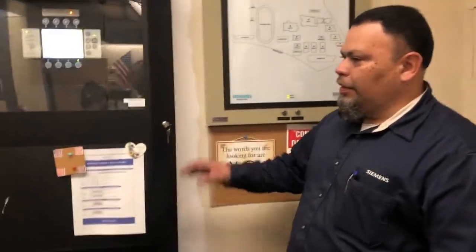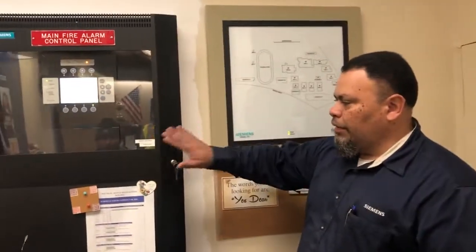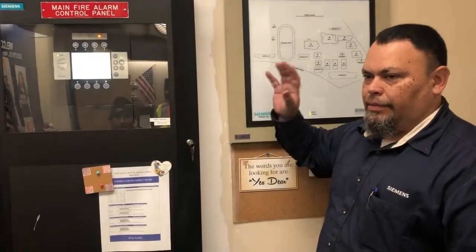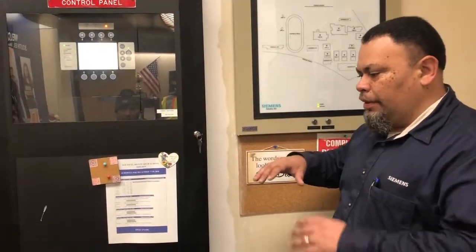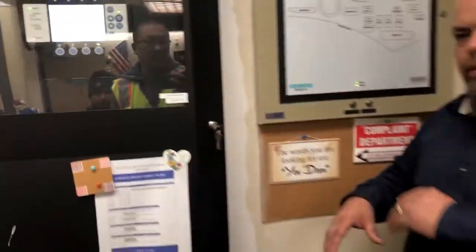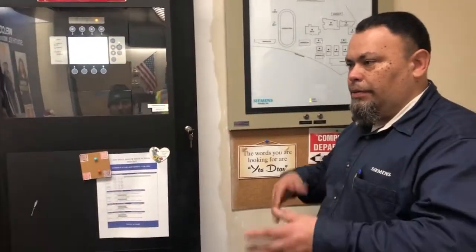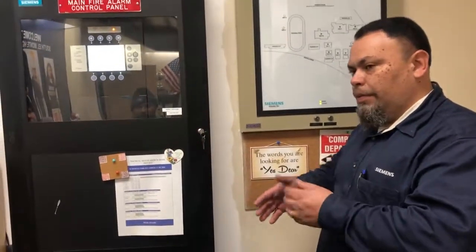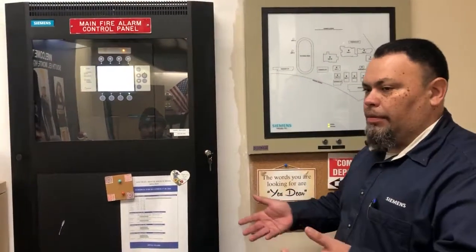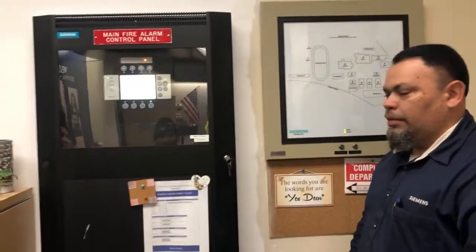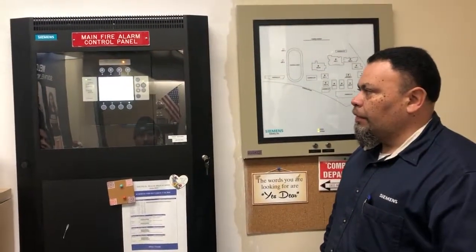So very important, if you guys are going to do a fire drill, call these people and put it on test. If you have a schedule of fire drills, like one every month, and you know what date it's going to be on, you can call them ahead of time, a couple of days or the day before, and say, tomorrow, between this time and this time, the system needs to be on test. So that's pretty much it.